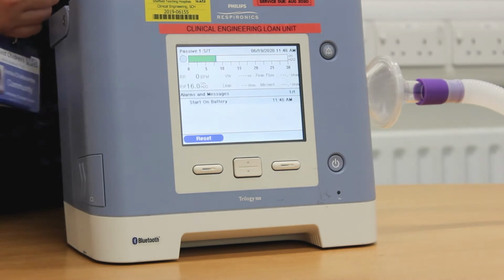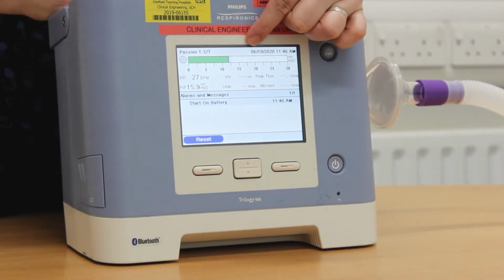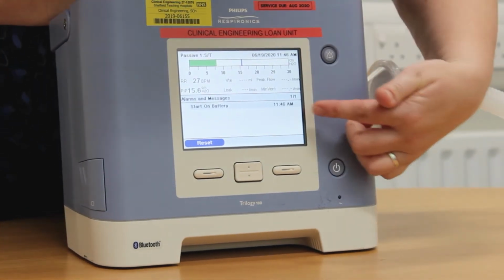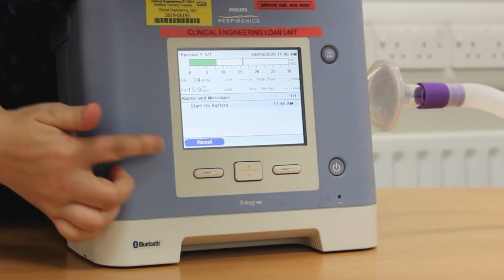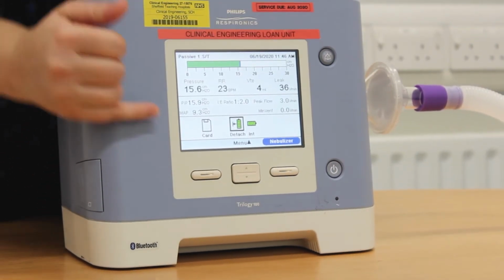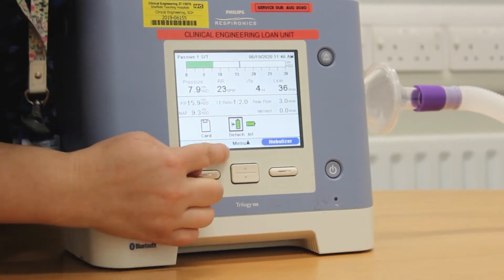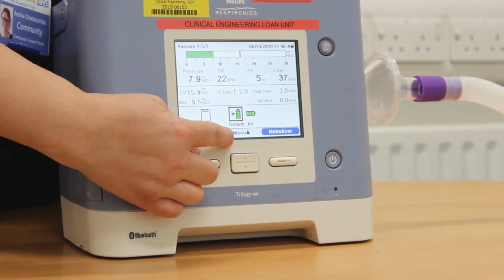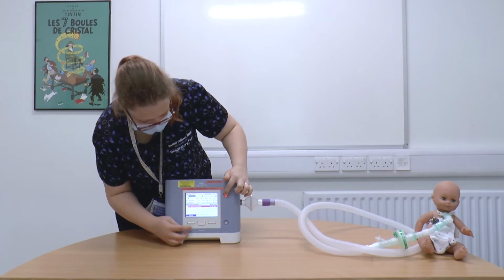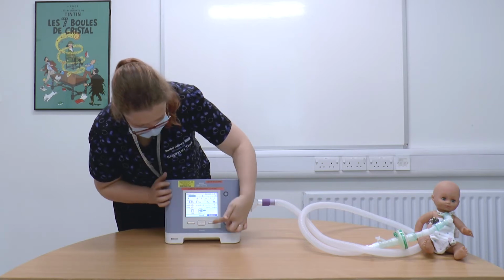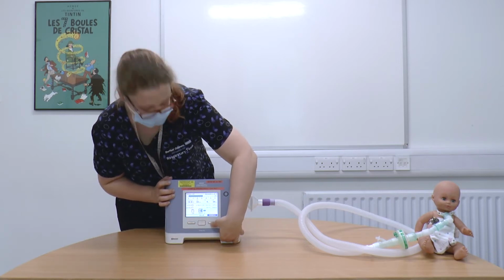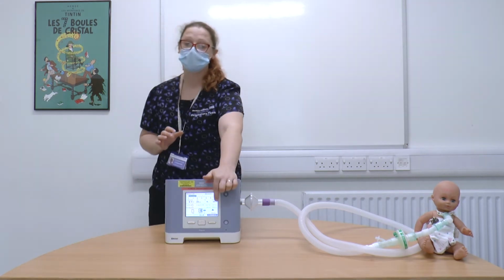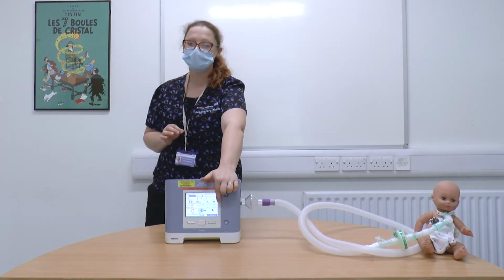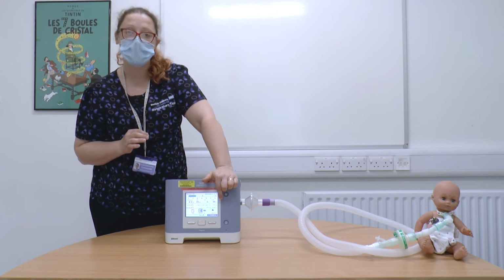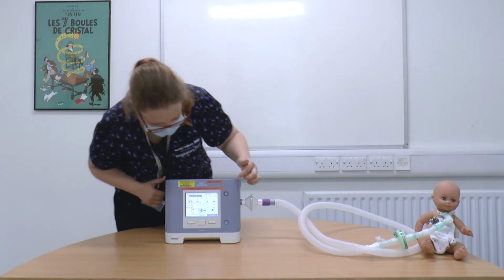You will see at the top the flow being delivered. You will see at the base, if no alarms have occurred, there is a choice of menu with up and down. If you have had a nebulizer enabled within the circuit, if you press the button highlighting nebulizer, a picture of a nebulizer tubing will appear, and that is to allow for a change of flow because higher flow occurs when the nebulizer is in use.